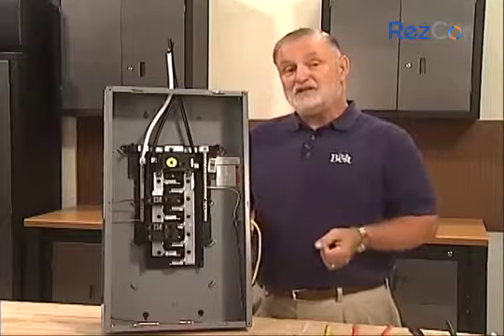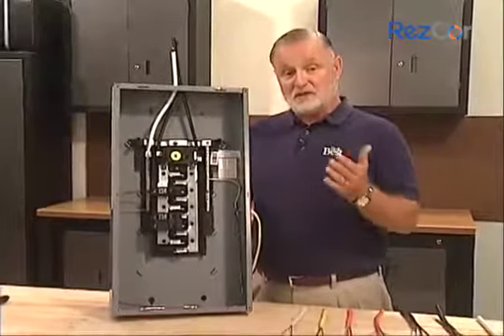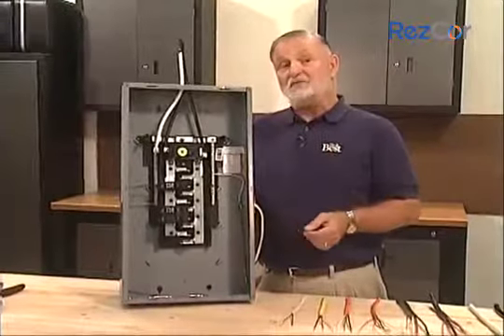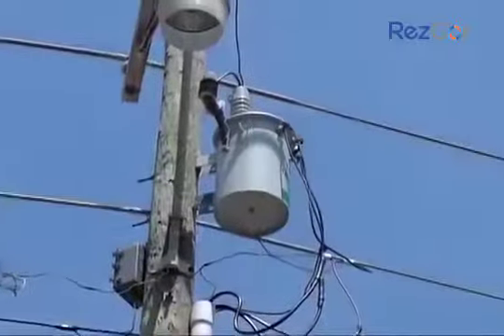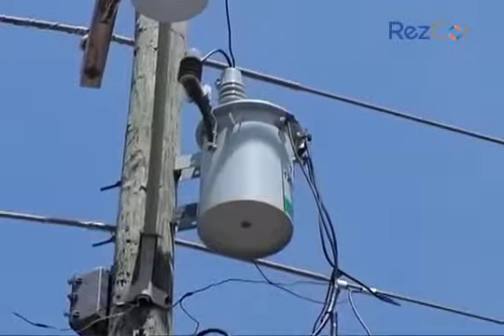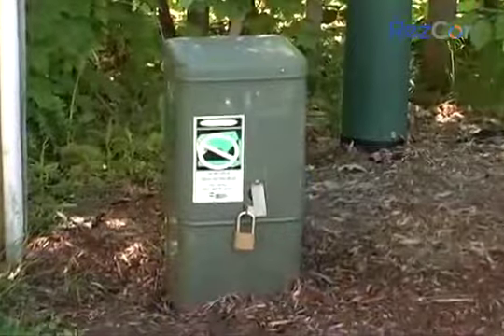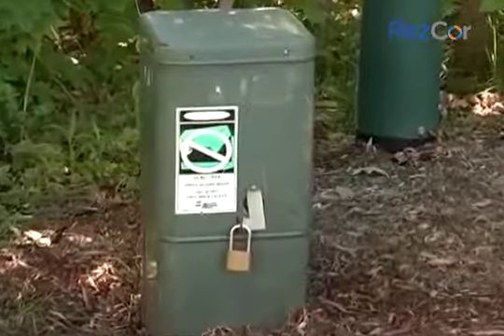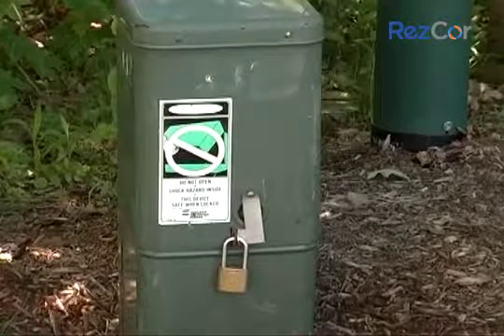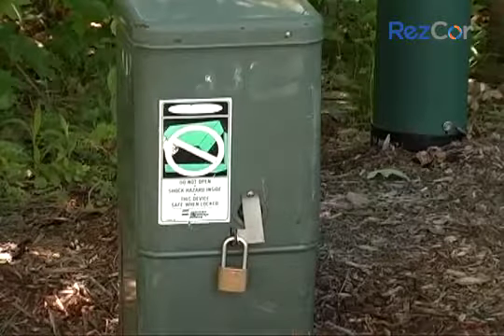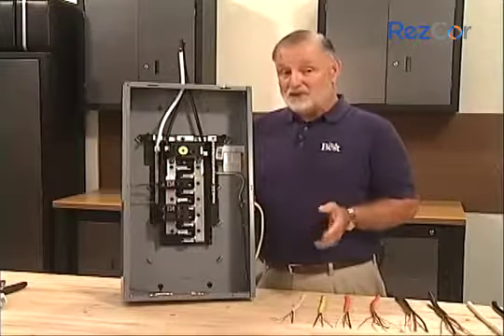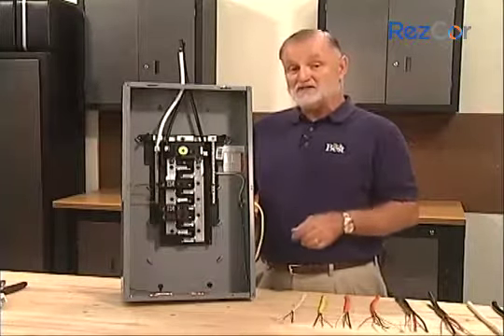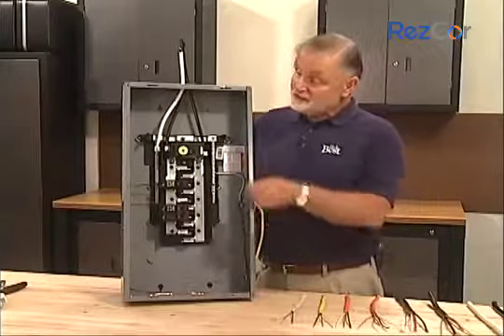The main panel receives electrical pressure, also known as voltage, from the electric company's transformer. The transformer is either hanging on a pole on the street or else it's located on the ground near the house. On the ground, the transformer is usually in the form of a big green box. The transformer supplies the voltage on two separate lines entering the house. These lines are known as a service entrance.